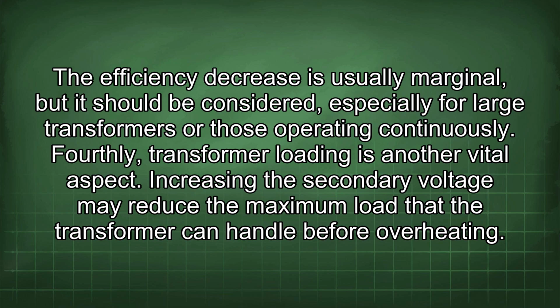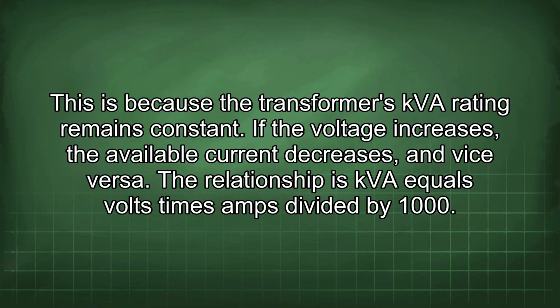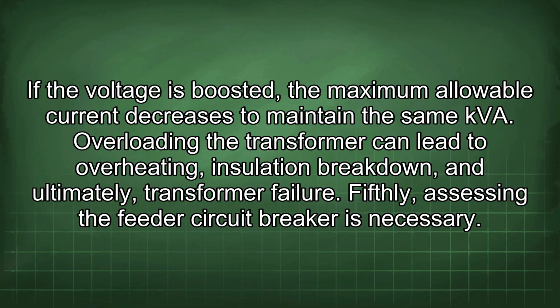Fourthly, transformer loading is another vital aspect. Increasing the secondary voltage may reduce the maximum load that the transformer can handle before overheating. This is because the transformer's kVA rating remains constant. If the voltage increases, the available current decreases, and vice versa. The relationship is kVA equals volts times amps divided by 1000. If the voltage is boosted, the maximum allowable current decreases to maintain the same kVA. Overloading the transformer can lead to overheating, insulation breakdown, and ultimately transformer failure.